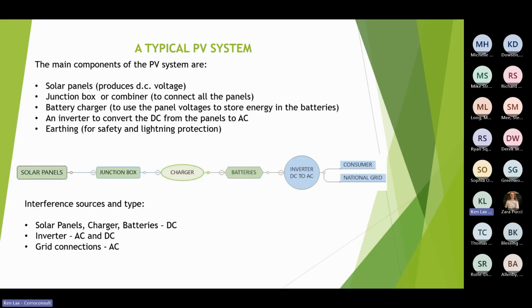And of course, when you could have easily in excess of 100,000 solar panels on a big site, you can get quite a lot of leakage current, which can get onto your pipe. So the first point is this isolation resistance, which has to be measured and controlled. Next goes into a junction box. So you've got cables going through the ground. Sometimes they're on cable trays, sometimes they're buried. And of course, any contractor will always choose the cheapest cable he can find on the basis, the well-founded engineering basis, that if it's cheaper, it must be better.